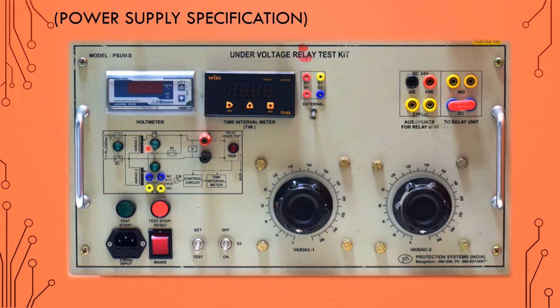And for safety purposes, we are giving the rated voltage of 110 volt directly, so that whatever clock setting is selected, the relay will be in normal operating mode only. So with variac 1, we will set the 110 volt, and we will set the fault voltage as per our observation table using variac 2. And this is the voltmeter used to read how much voltage we are feeding to the relay.